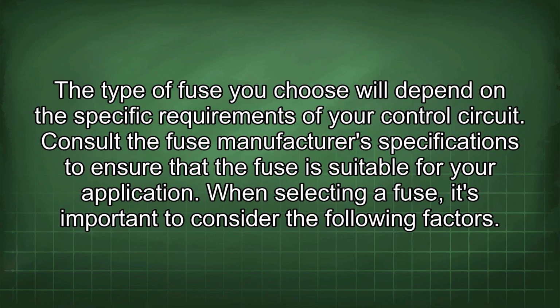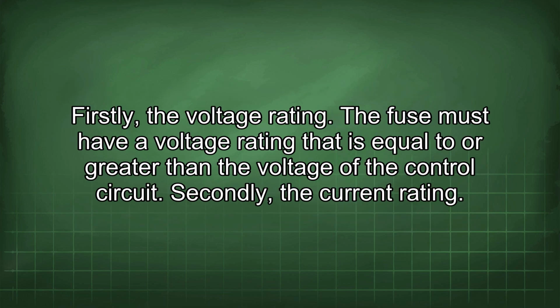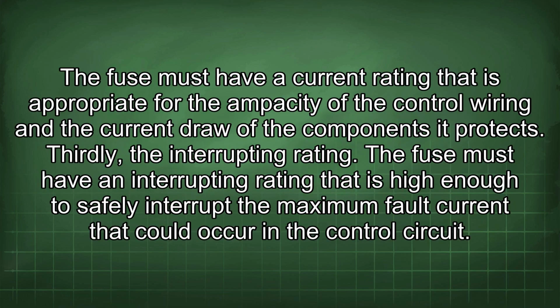The type of fuse you choose will depend on the specific requirements of your control circuit. Consult the fuse manufacturer's specifications to ensure that the fuse is suitable for your application. When selecting a fuse, it's important to consider the following factors. Firstly, the voltage rating. The fuse must have a voltage rating that is equal to or greater than the voltage of the control circuit. Secondly, the current rating. The fuse must have a current rating that is appropriate for the ampacity of the control wiring and the current draw of the components it protects.